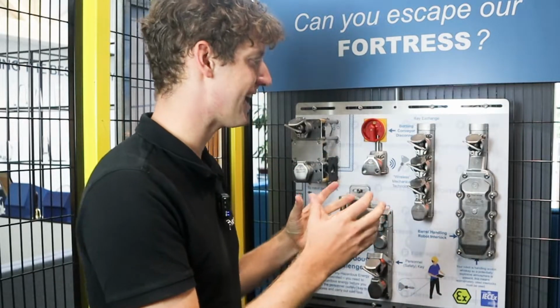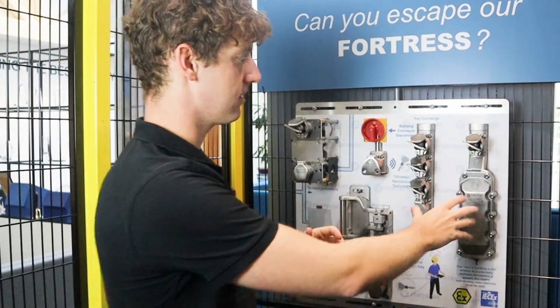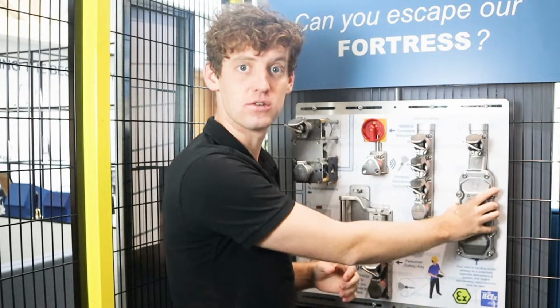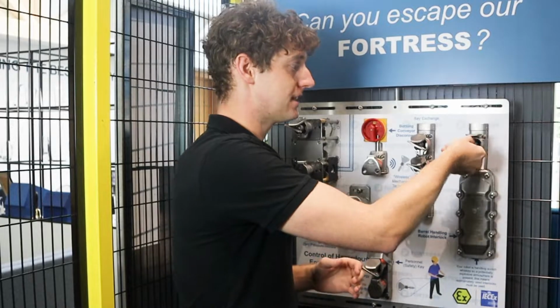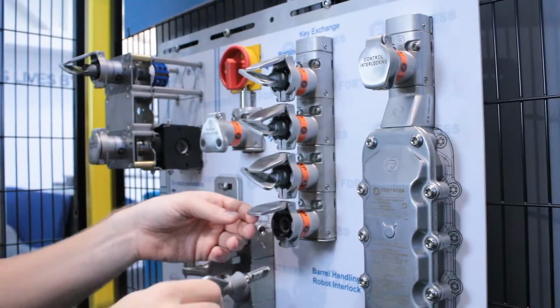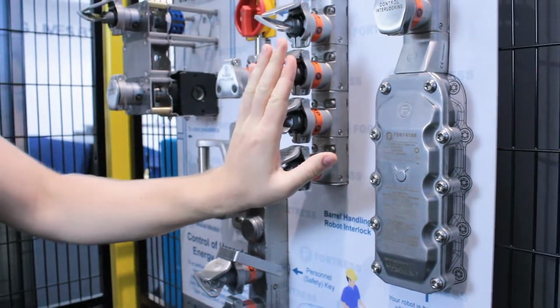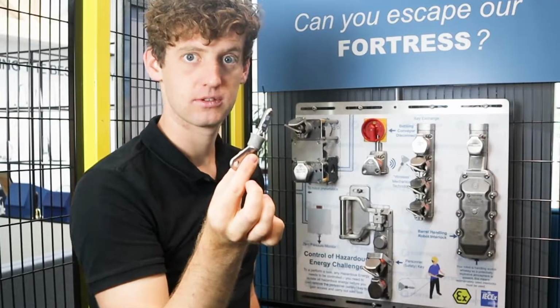Because this machine is handling barrels of Scotch whiskey, there's a slight risk of an explosion occurring from some of the ethanol that can seep out of the barrels. For this reason, this switch here to turn off some of the machinery is actually rated to be used in a hazardous environment where there's a chance of an explosion. This key here will flick this switch to turn off that machine, and I can use this key to put it as the final key into my key exchange. Once I've done that, I can now take the access key out of the key exchange box.